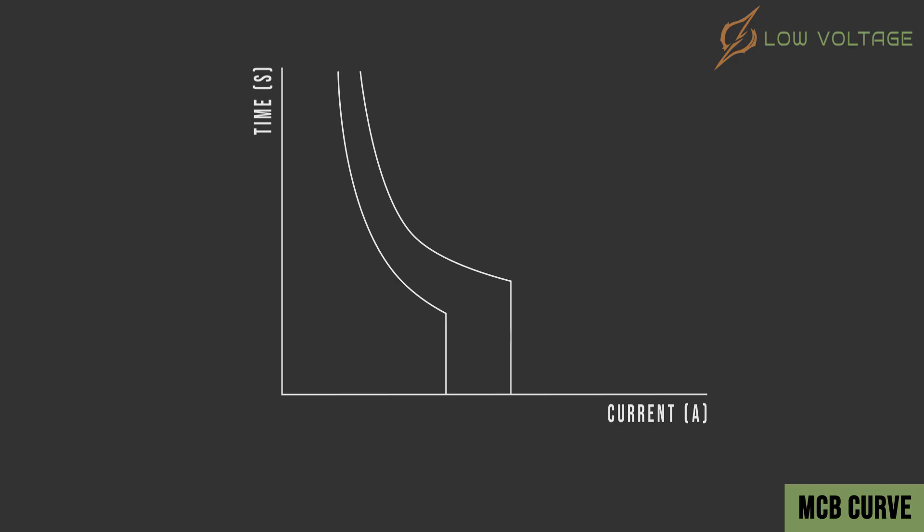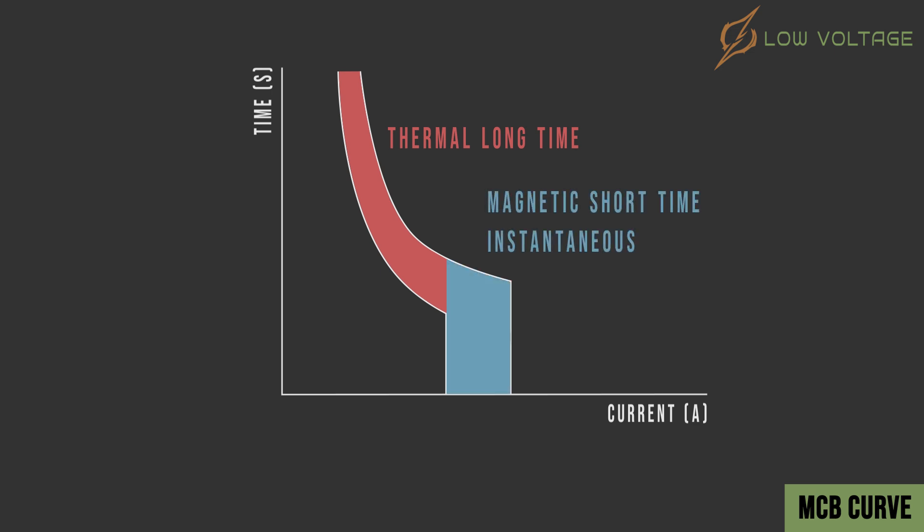The MCB Curve has two zones. The first zone is for long-time thermal protection, and the second zone is for short-time instantaneous electromagnetic protection. Miniature circuit breakers have rated current IN that defines long-time thermal trip setting. They also have magnetic trip range, which is minimum and maximum magnetic currents. This range defines short-time instantaneous magnetic settings.